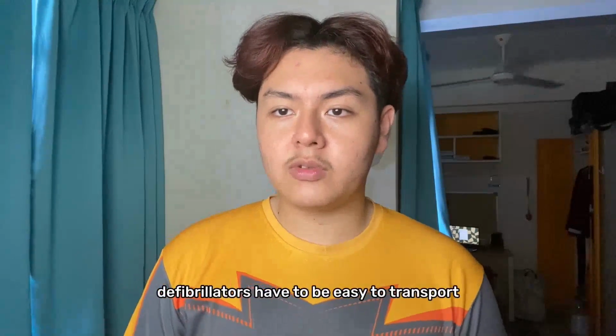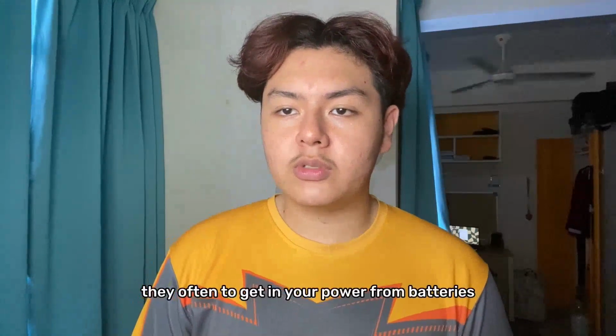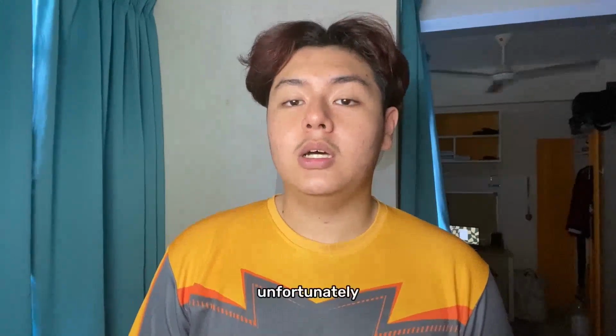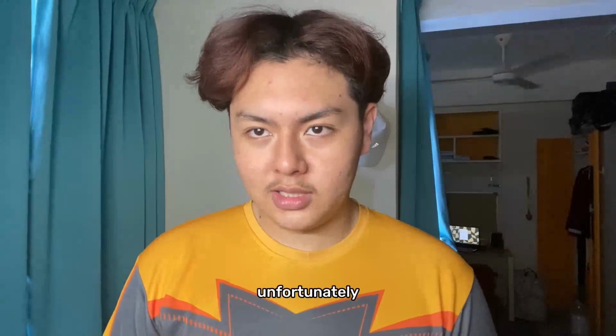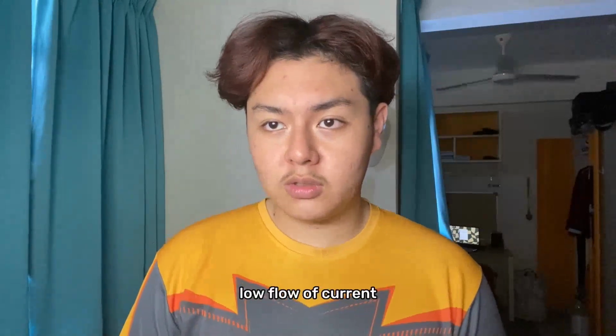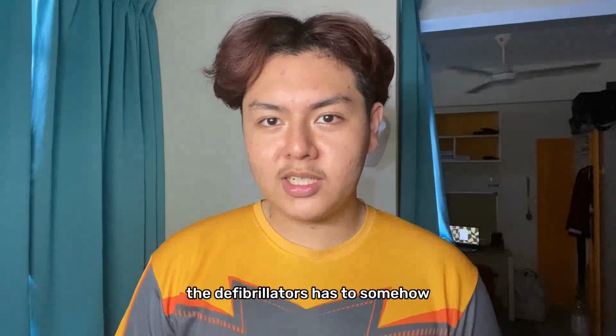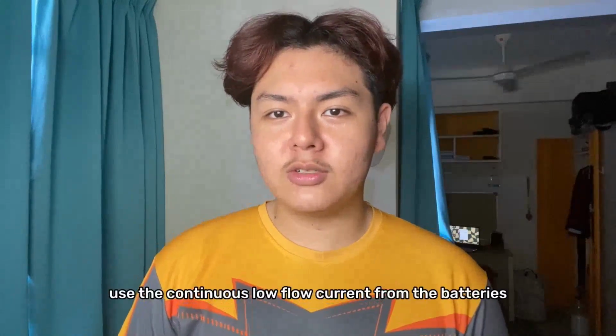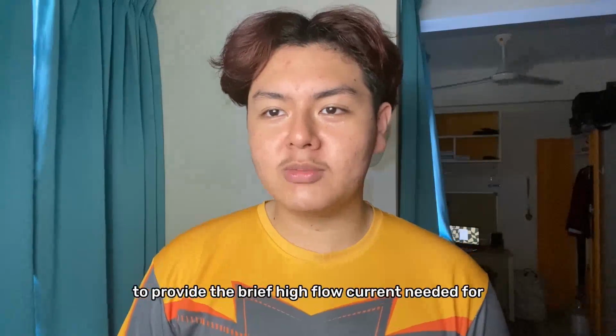Defibrillators have to be easy to transport. They often get their power from batteries. Unfortunately, batteries can only produce a continuous low flow of current. The defibrillator has to somehow use the continuous low flow current from the batteries to provide the brief high flow current needed for defibrillation.